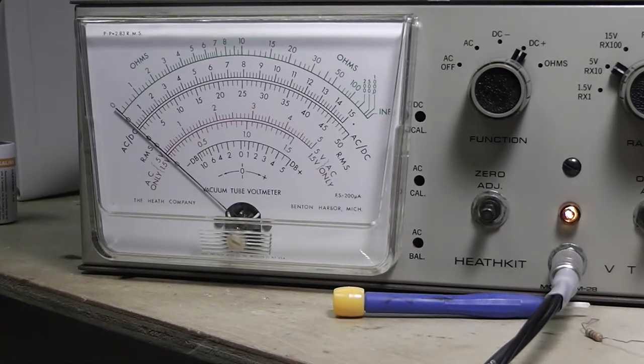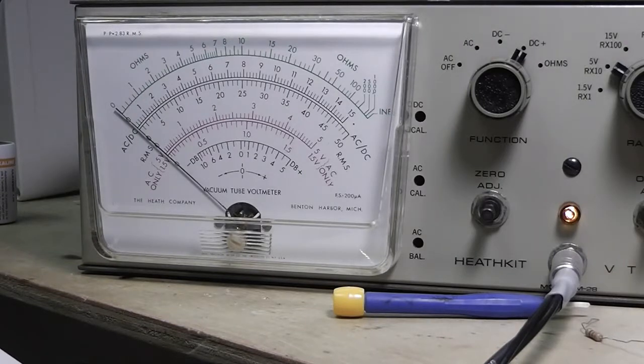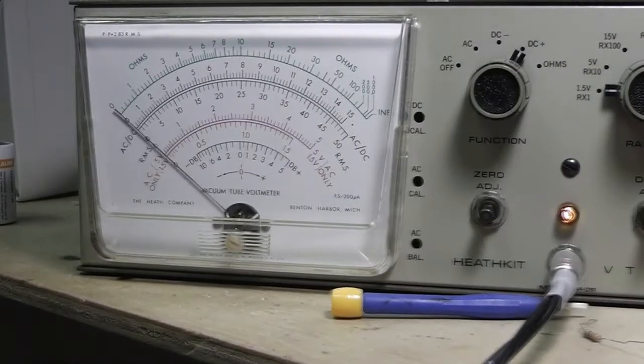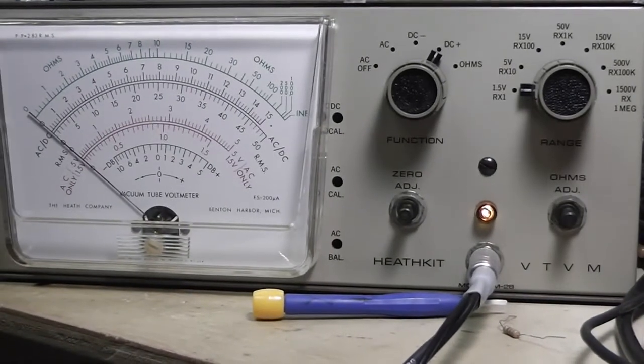Alright, set the function switch to DC plus, which we do. The range switch should be to 1.5 volts. So put that down over there. Connect the probe and the common test leads to the flashlight battery and adjust the DC calibration control so that the meter pointer falls directly over the small red dot on the meter face.